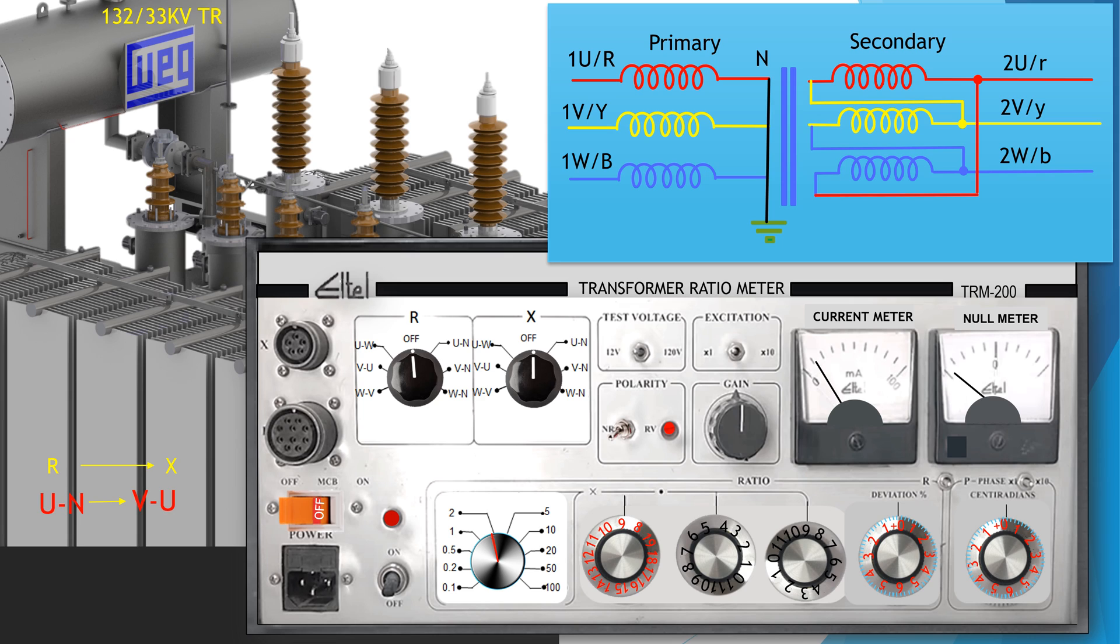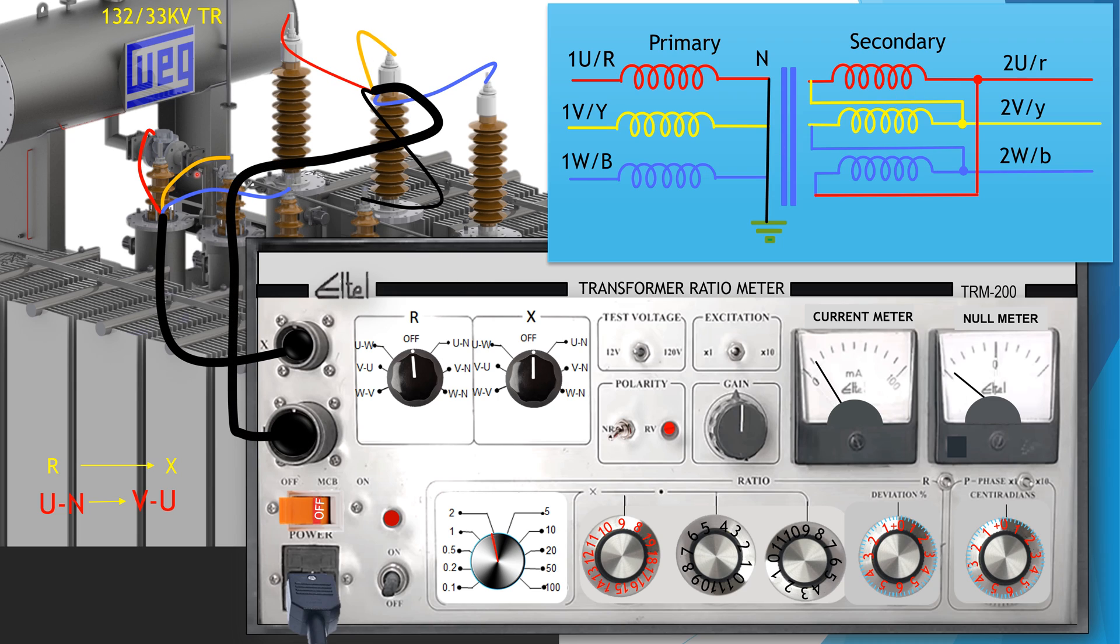We shall conduct test on red phase, that is U phase as per testing kit. Primary side phase setting will be between U and N and secondary side phase setting will be between V and U, the same phase of the two different windings of the transformer.